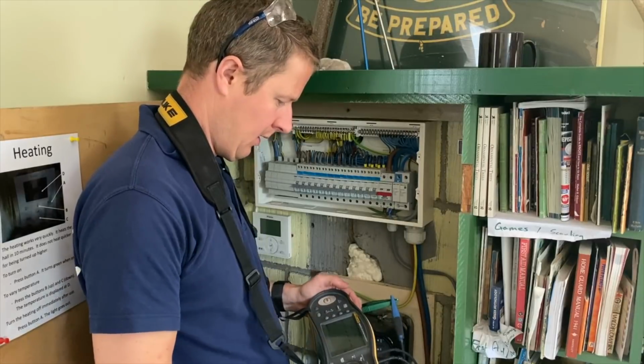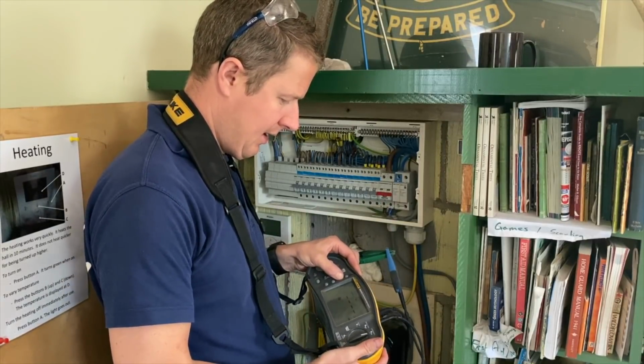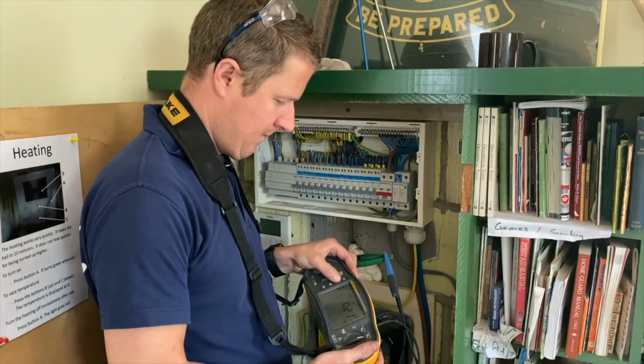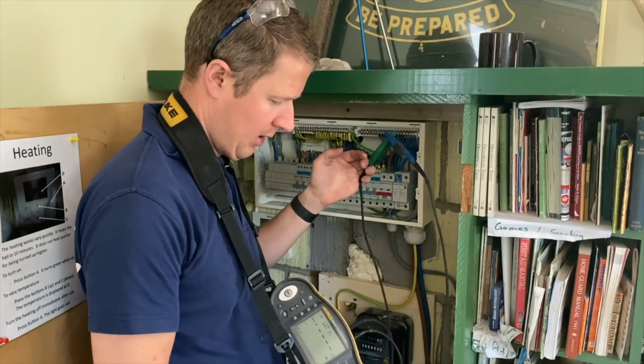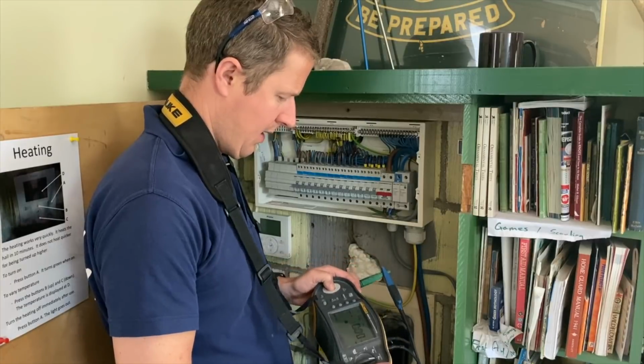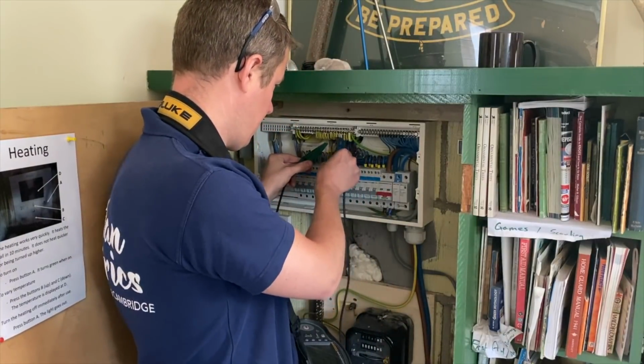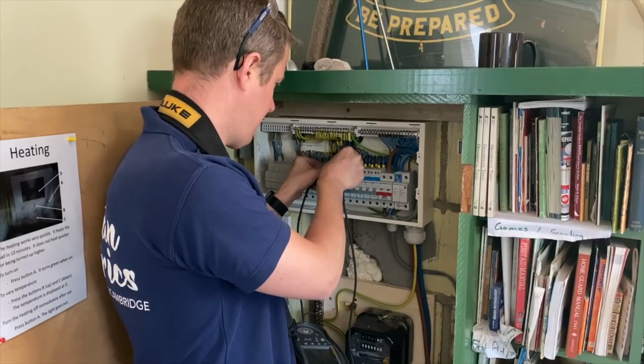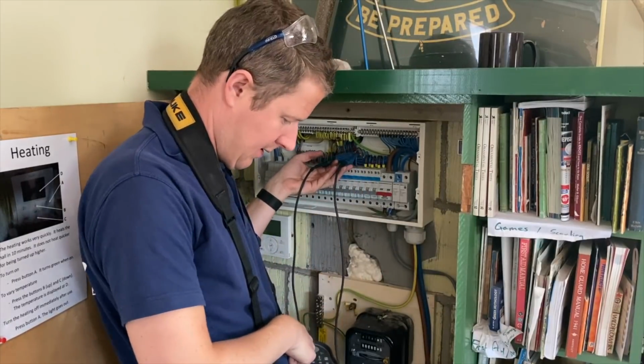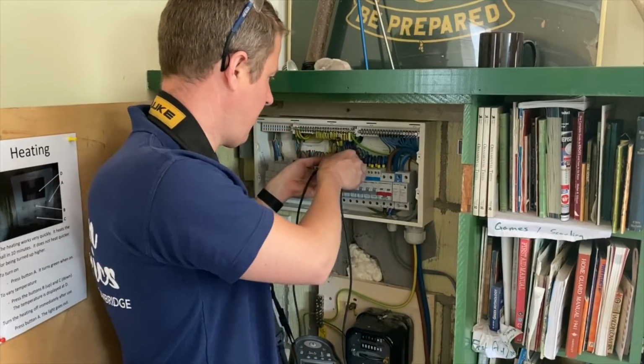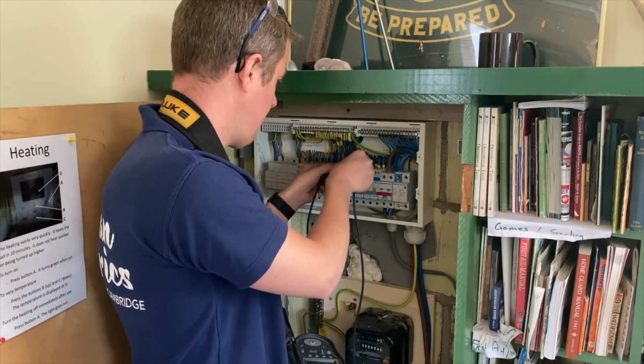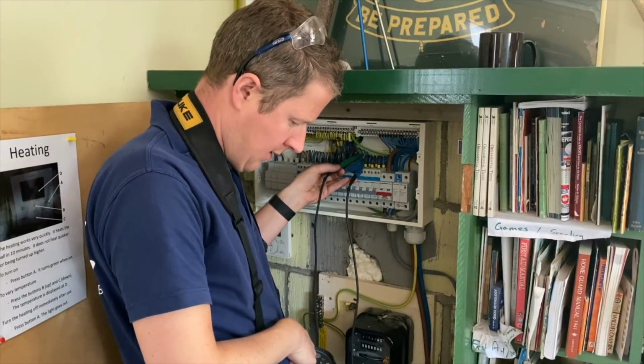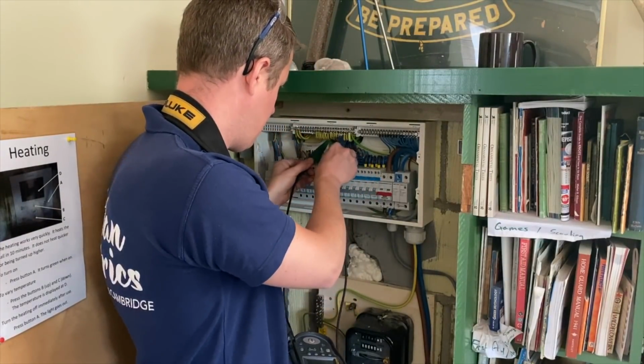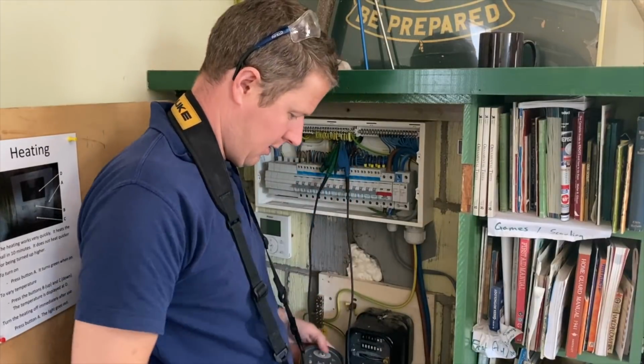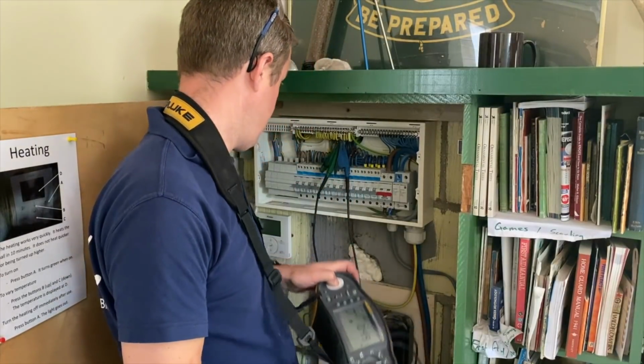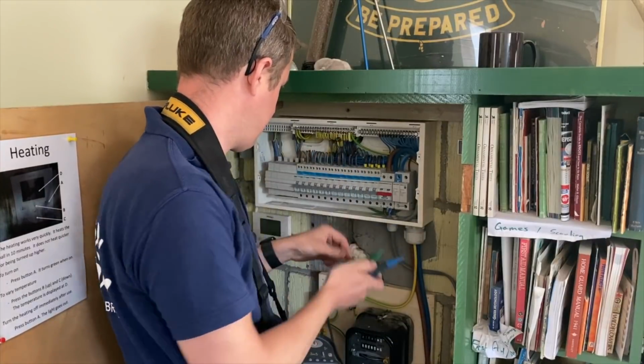So I've got to zero my leads again because I zeroed them to my long wander lead. Now I've only got these short leads, so I've got to zero them. There we go. And we'll start by doing the continuity of the phase conductor, as that's the order that it is on the certificate. 0.27 ohms. Then we'll do the neutral conductors, 0.29 ohms. And then the CPC conductors, 0.49 ohms. So that's good, very good readings.